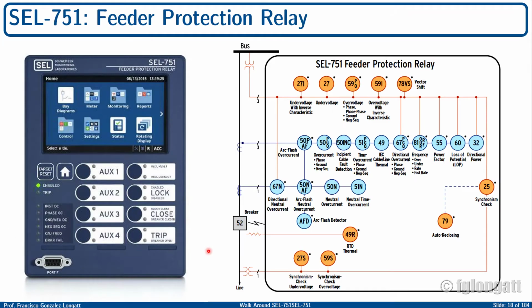Here you can see a set of the very different protection functionalities inside this device. As you can see, this is a very complete relay, including protections starting from under voltage, including the inverse characteristic, going across over voltage and going deeper into vector shift, directional power, loss of potential, and of course the classical features like the classical time overcurrent for phase, ground and negative sequence, and the classical instantaneous current for phase, ground and negative sequence. Okay, this is a very well equipped device.